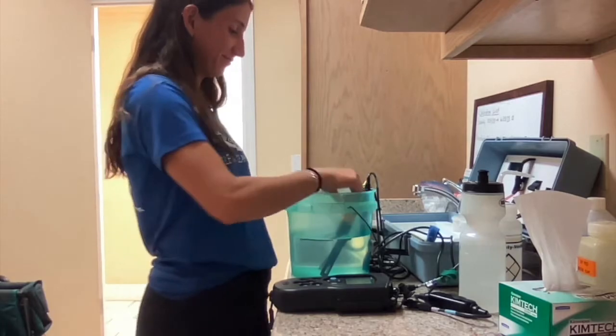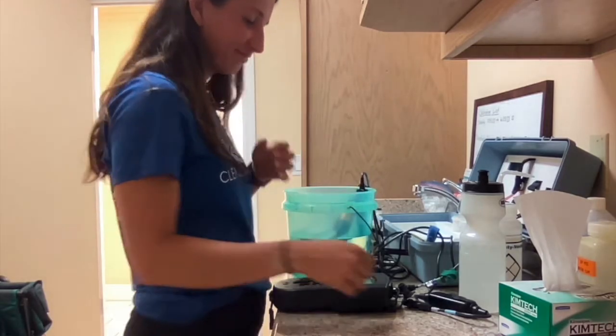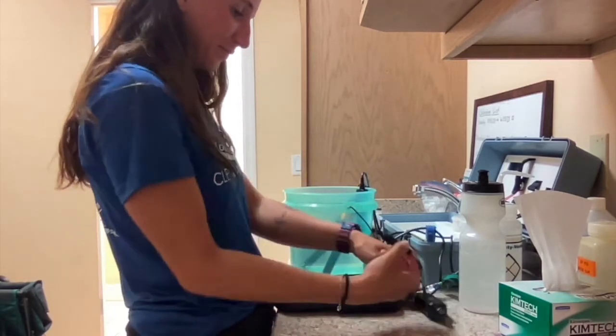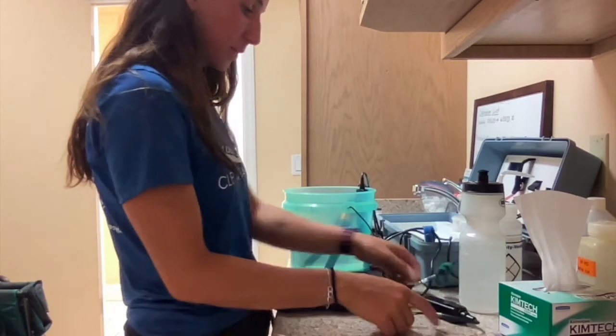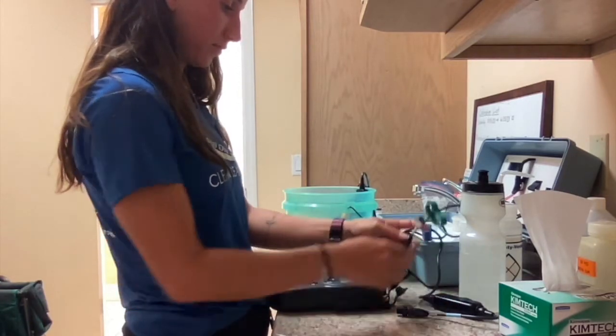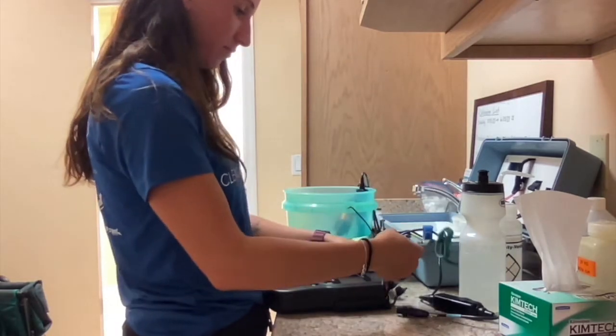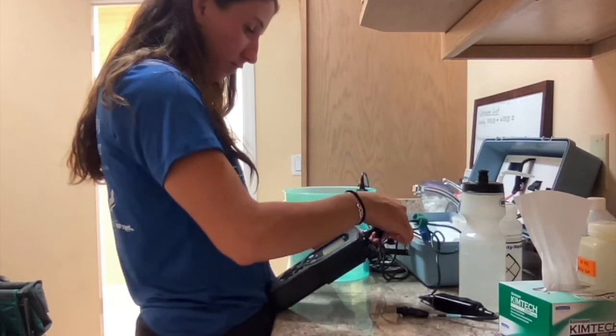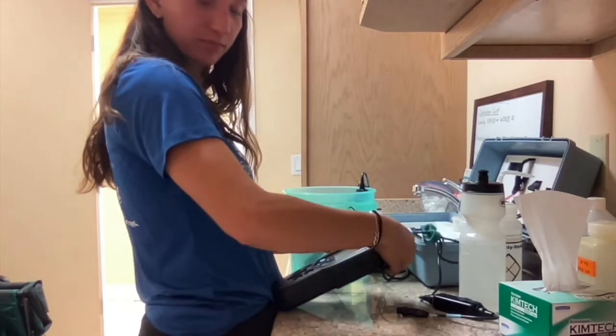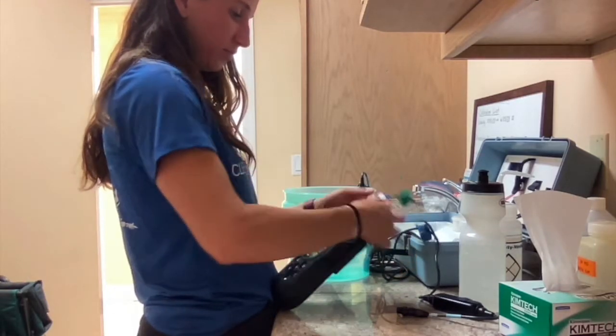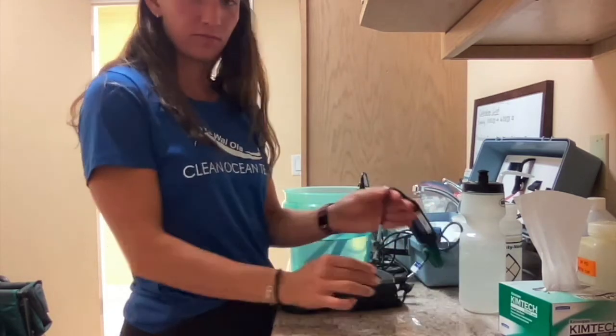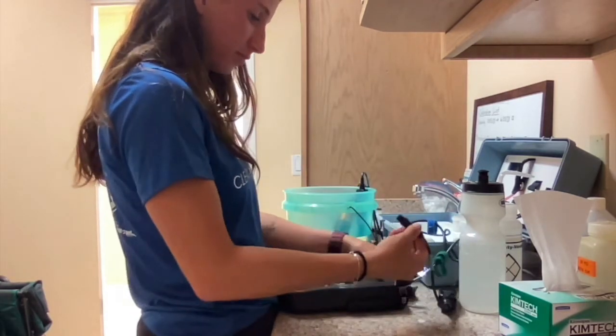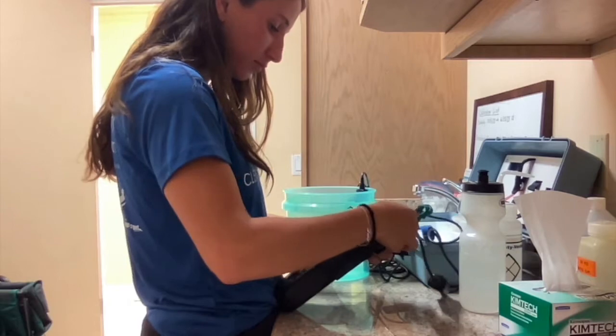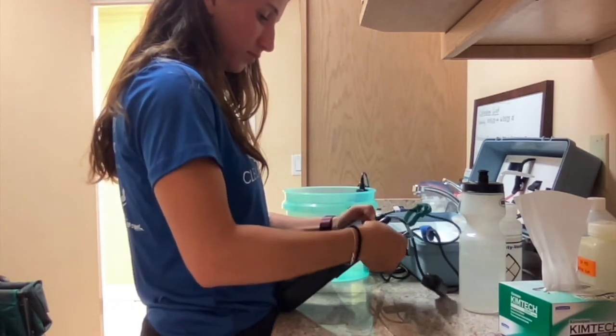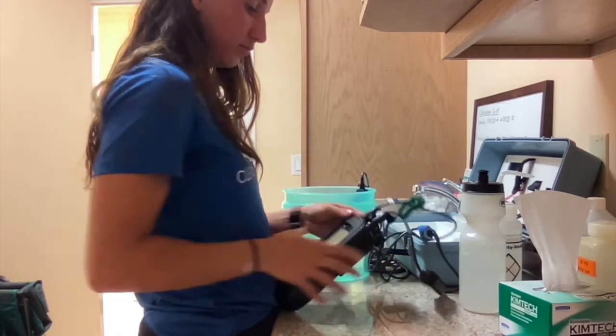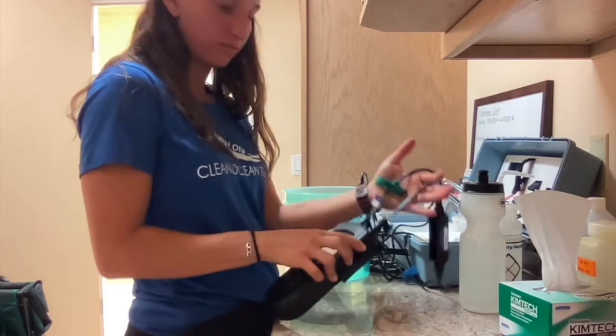While you're waiting, you can plug the probes into the meter and also get things ready to do turbidity measurements, but that will be on another instruction video. First, plug in the salinity and DO probes. Accurate DO readings depend upon the salinity of the water, so you must always have both of these probes connected at the same time. Plug the blue cord above the green button and the green cord above the blue button. By doing this, you'll ensure that the readings align with the order on the datasheet. If cords are not plugged in this manner, use the units of each measurement to identify which parameter is which.